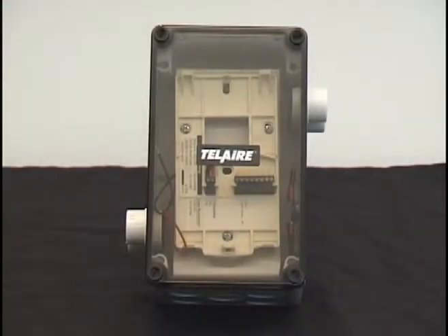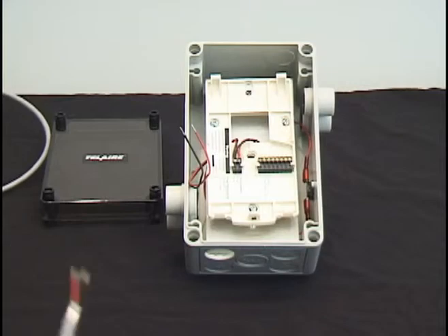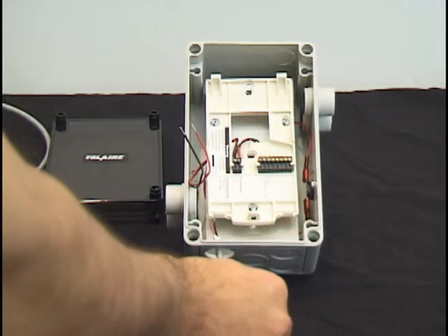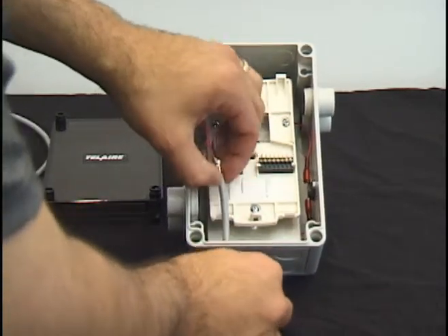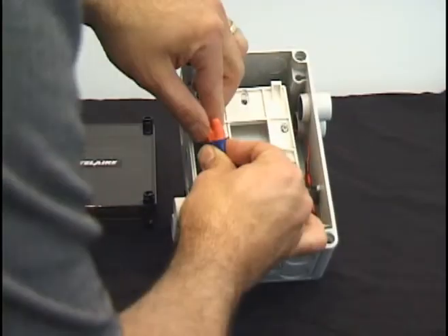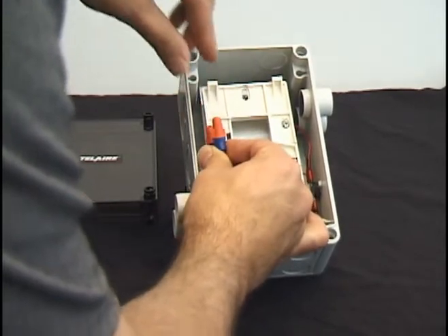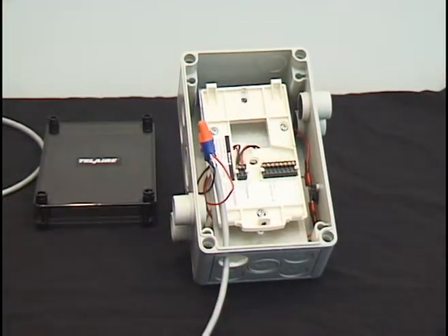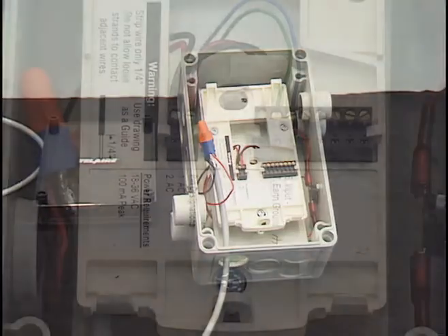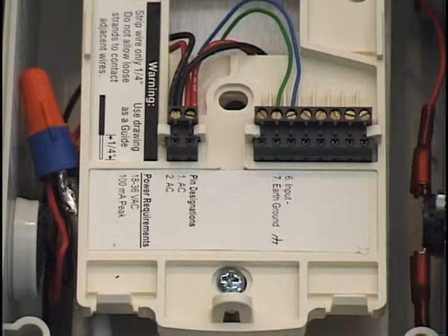If you are mounting the VaporStat outdoors, use the outdoor air enclosure, model number 1551. Bring wiring into the outside air box via one of the available conduit knockouts. Connect the 24-volt power wires to the red and black pigtails using wire nuts. Connect the sensor outputs to the IOM as previously illustrated.